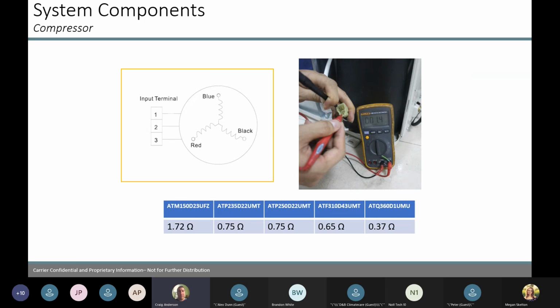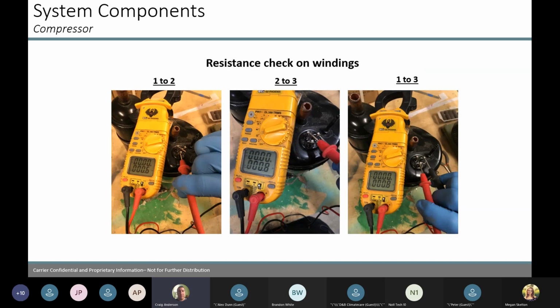Compressor as well. We're checking resistance between all the circuits. Most DC compressors, this is how we're going to check them, similar to DC motors, stuff like that. We're checking the resistance between the windings, and when we're checking them, all should be pretty much equal. We're checking it from 1 to 2, from 2 to 3, and then from 1 to 3. They all should be close.